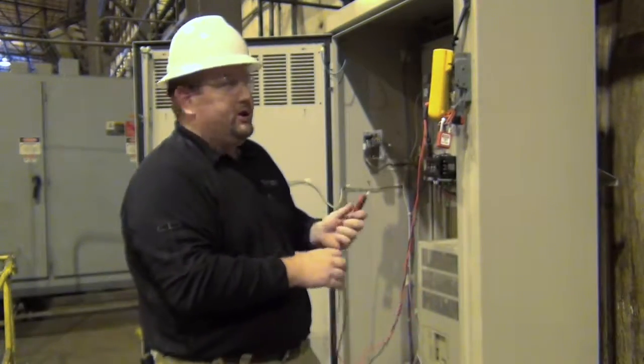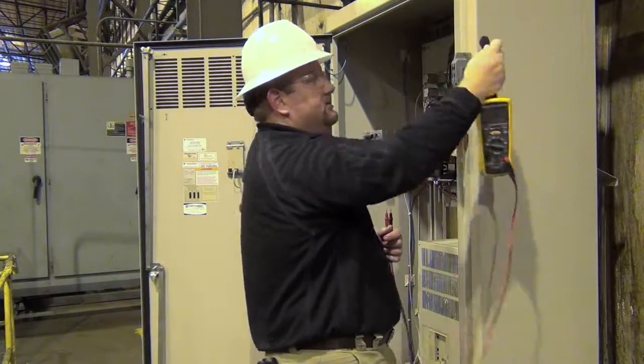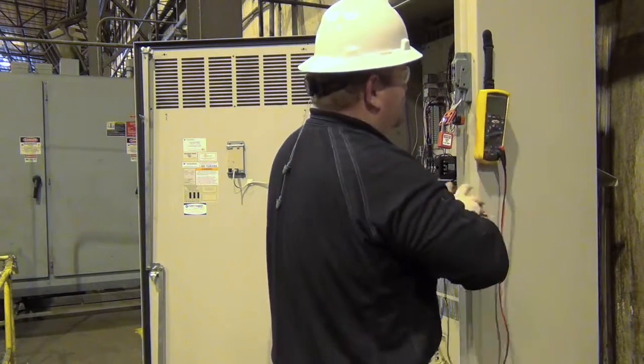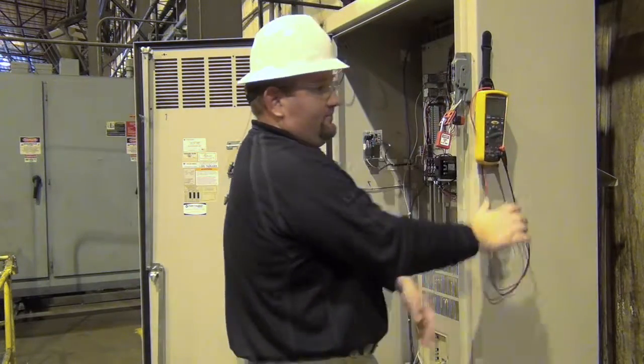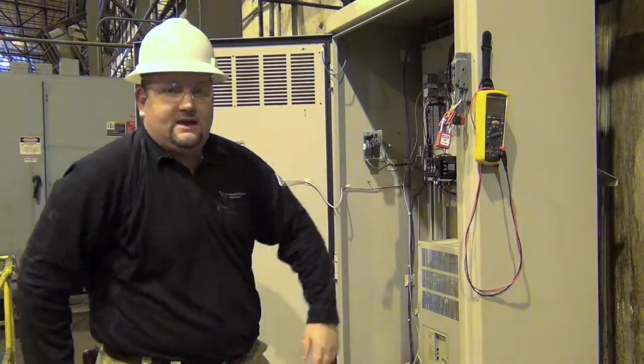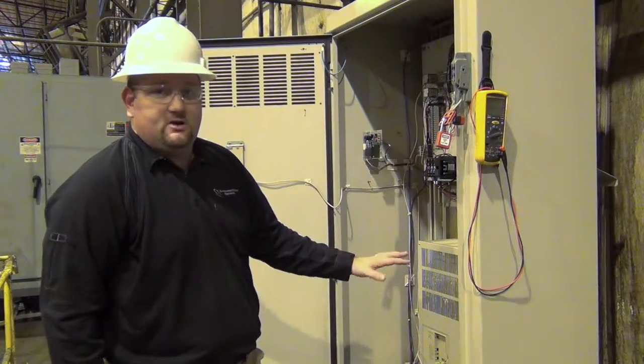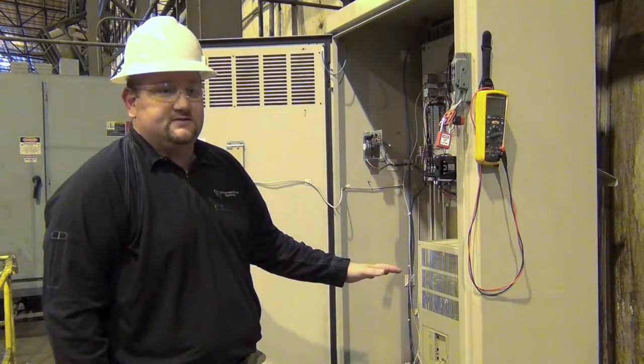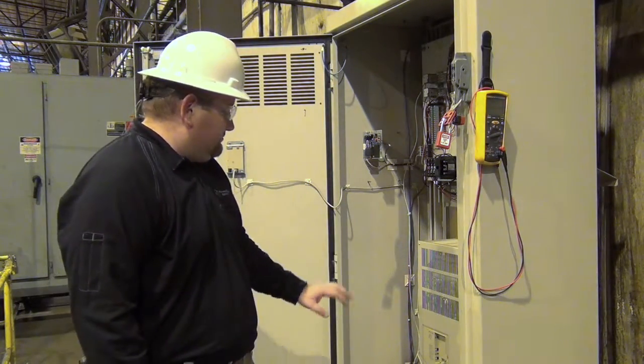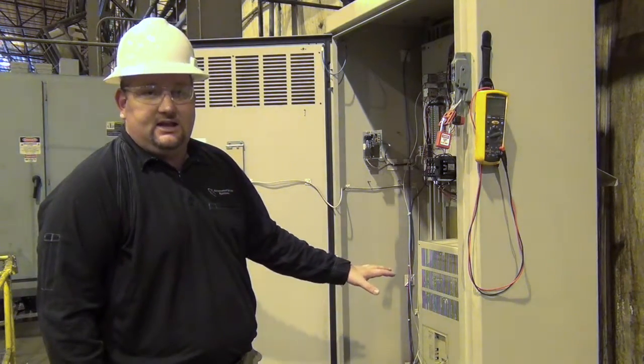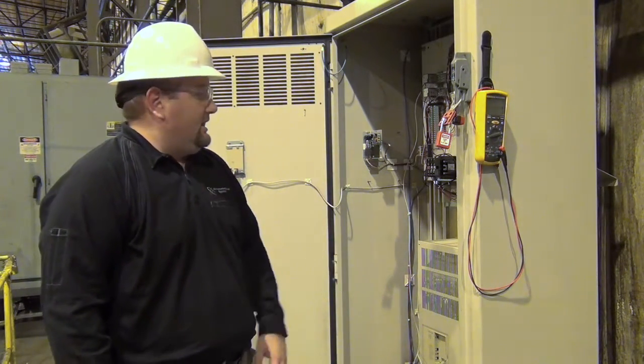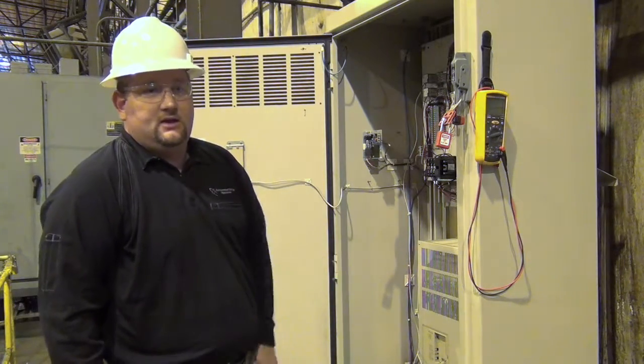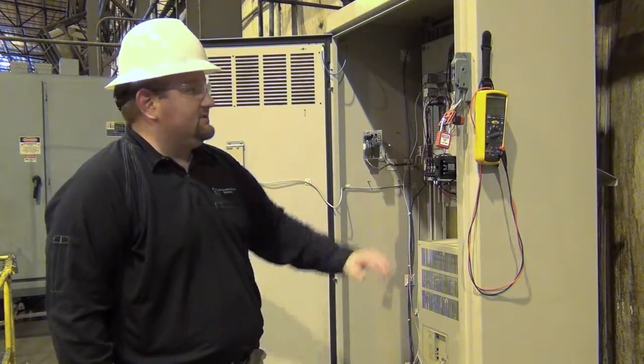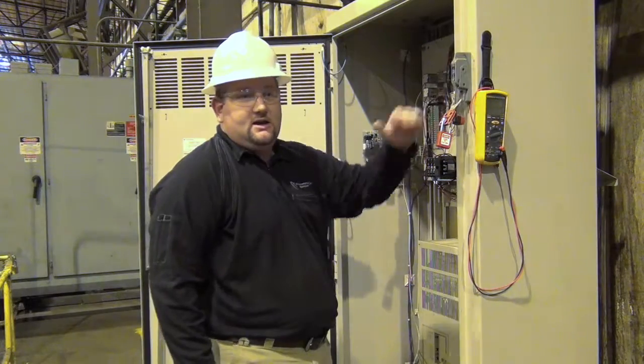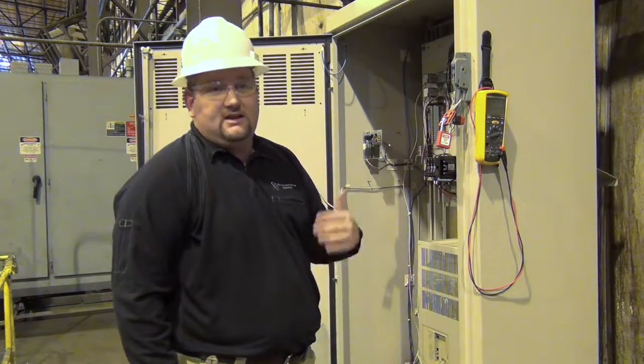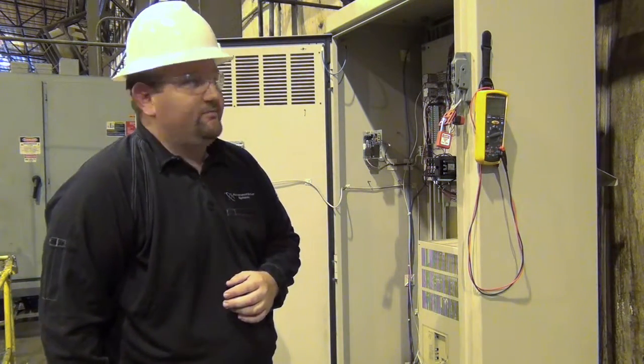So the other critical point at this stage is if you had just powered this drive down, all drives have a DC bus circuit, and that DC bus circuit will typically have somewhere in the vicinity of 700 volts on it if it's a 480 volt drive. Certain models of drives have an LED indicator of the DC charge. Don't ever trust it. A good rule of thumb for safe practices is once you actuate the disconnect, you should wait at least 10 minutes to verify that that bus has gotten to a safe level.